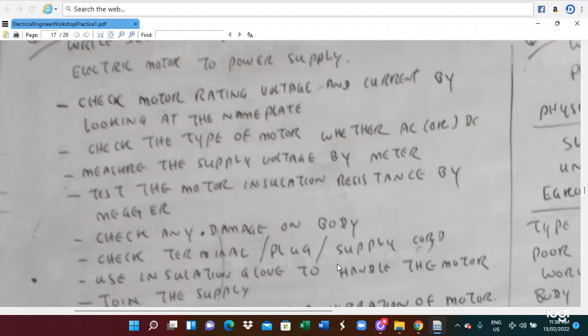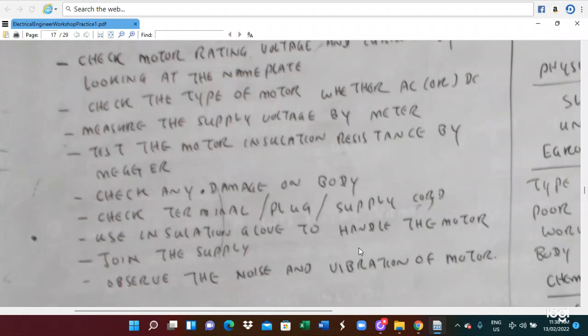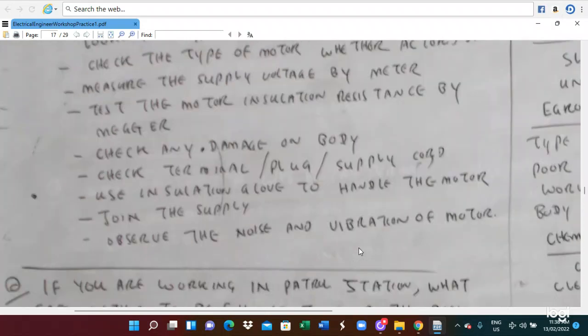You have to measure the supply voltage with the meter. You have to test the motor insulation resistance with the megger, and check for any damage on the body. You have to check the terminal and supply cord, use insulation glove to handle the motor and join the supply.